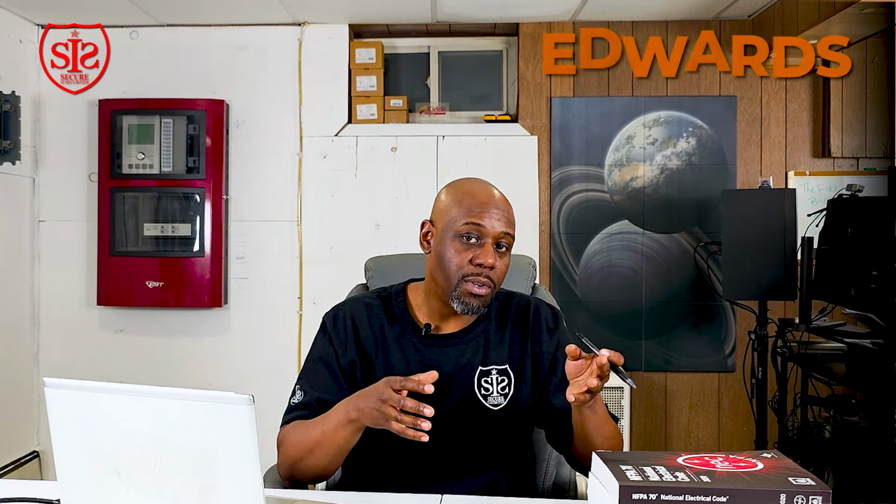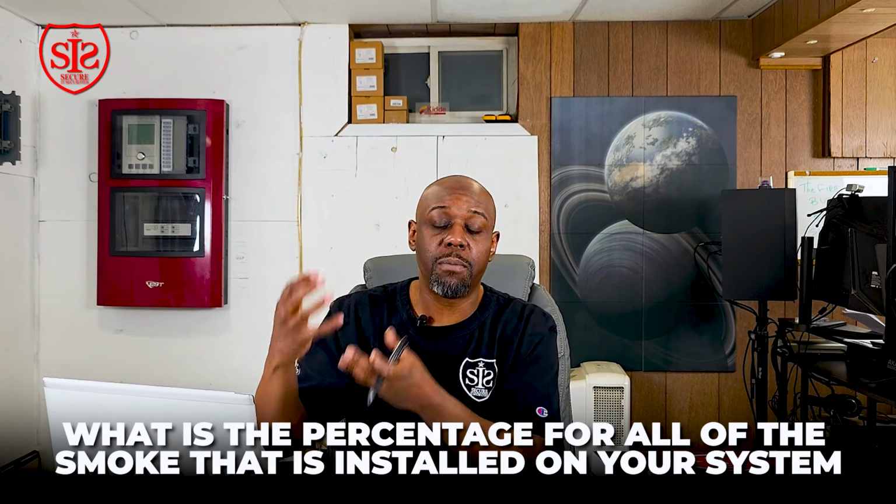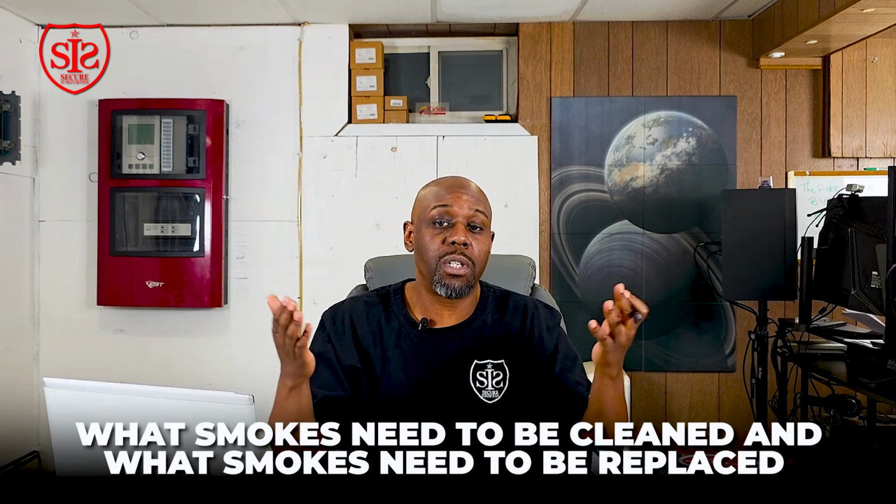Now, specific to an Edwards system, you may get a maintenance fault. At the time you get a maintenance fault, that means that detector is 80% dirty. There's nothing you can do about it. That device needs to be replaced, and it's going to put a monitoring trouble on your system. At that point, if anything happened in that particular area, that device will not go into alarm. So it's your job to know what the percentage is for all of the smokes installed on your system. You can do a report for less than 20 and also less than 80, so that way you can figure out what smokes need to be cleaned and what smokes need to be replaced.